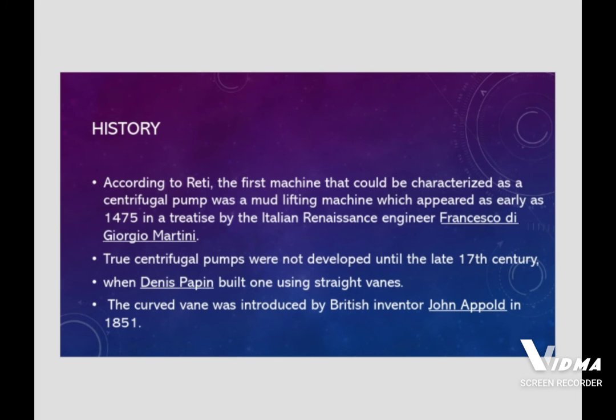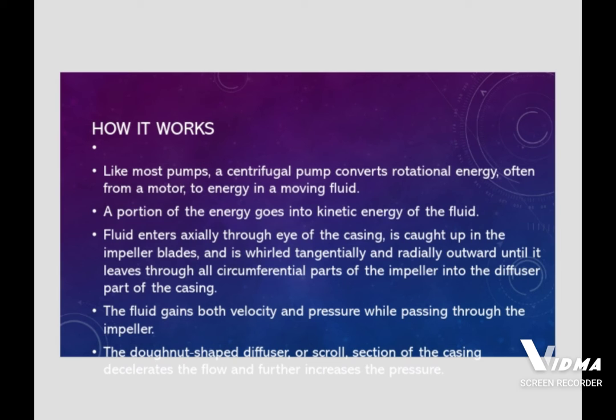Like most pumps, a centrifugal pump converts rotational energy — often from a motor — to energy in the moving fluid. A portion of the energy goes into kinetic energy of the fluid. The fluid enters axially through the eye of the casing, is caught up in the impeller blades, and is whirled tangentially and radially outward until it leaves through all circumferential parts of the impeller into the diffuser part of the casing. The fluid gains both velocity and pressure while passing through the impeller.